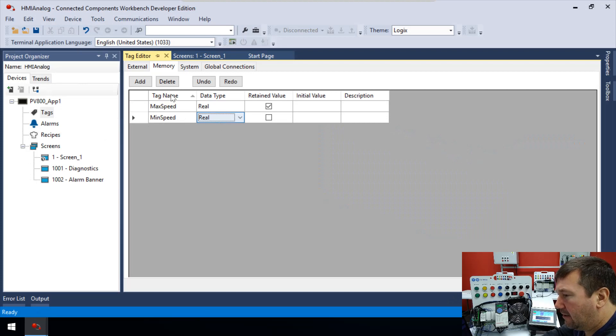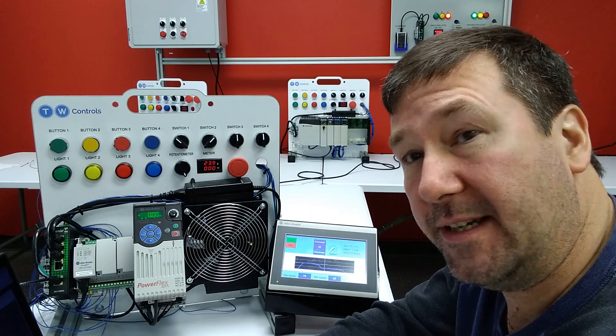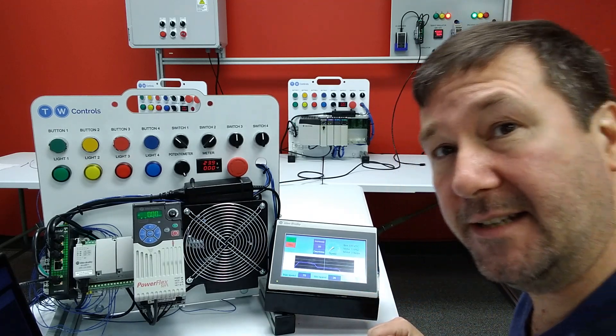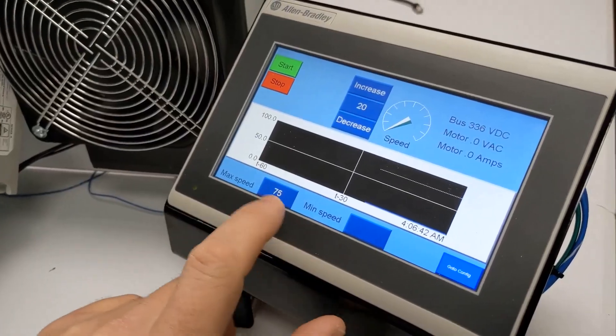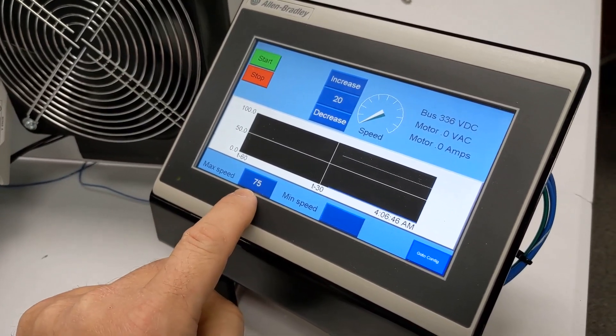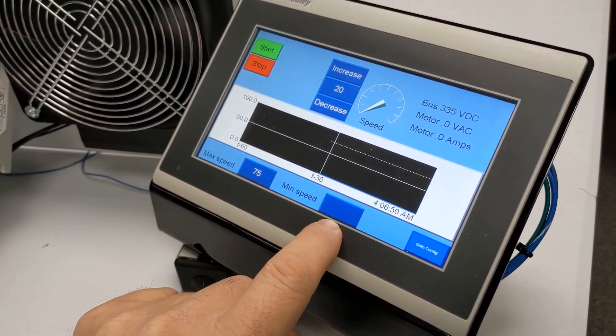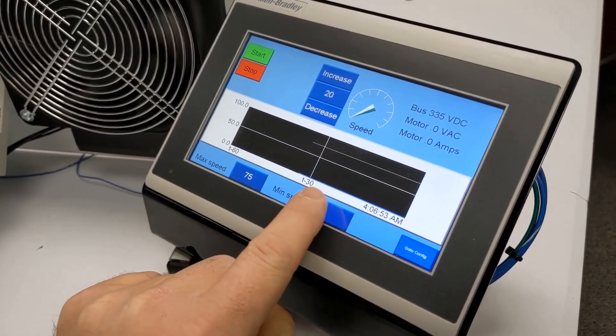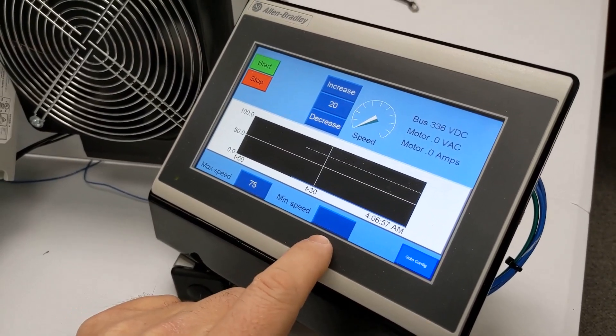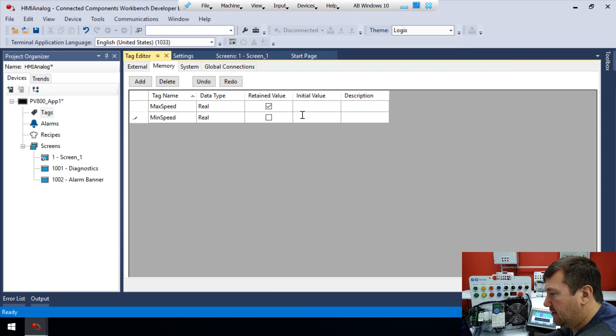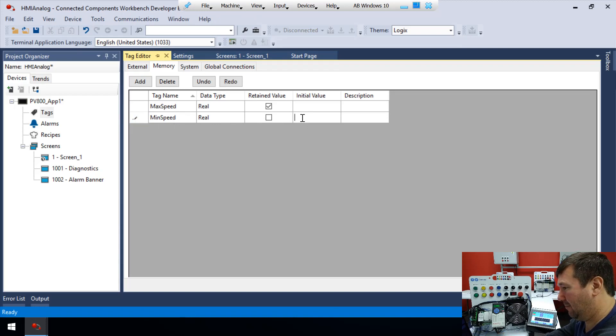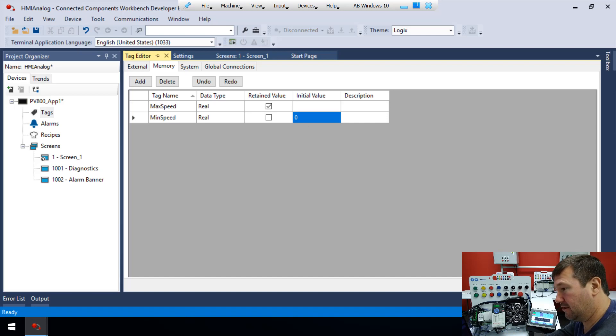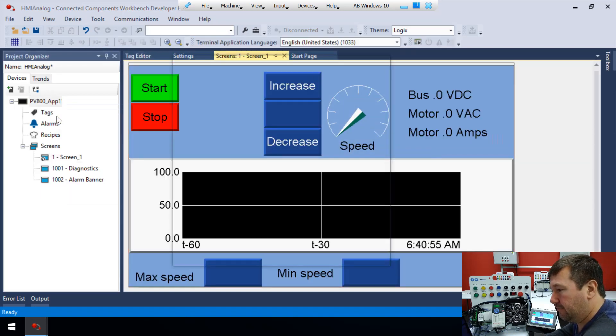And so let's talk about these two values because obviously they went to zero. So looking back at our tags, we had checked the retained value here. So what I want to do now is I want to cycle the power on our HMI and see what it looks like when we power it back up. Now we're powered back up. You see our max speed, we still have 75 in, but see our min speed is now blank. Also notice that it doesn't show a value at all. And I don't like that. So first let's fix this. So let's go to our tag editor and on our min speed here, let's put an initial value in. And I really think there should be a different way to do this. This is the only way I figured it out. So if I put a zero right there on the initial value, well, actually we're going to, in a second, we're going to change it. Let's stick with a zero just so we can see that this works.